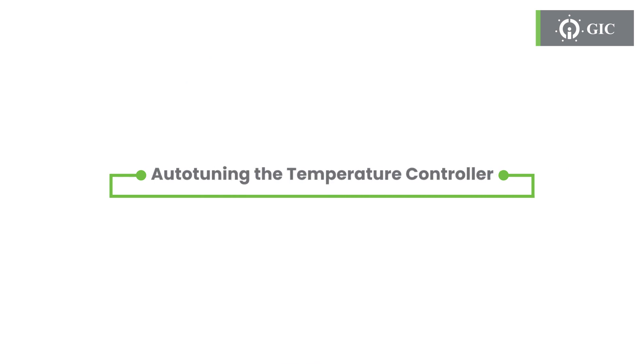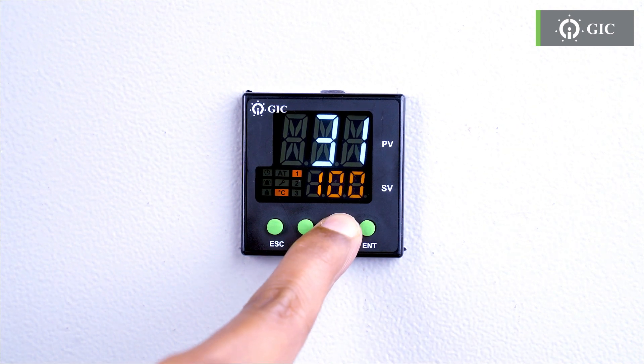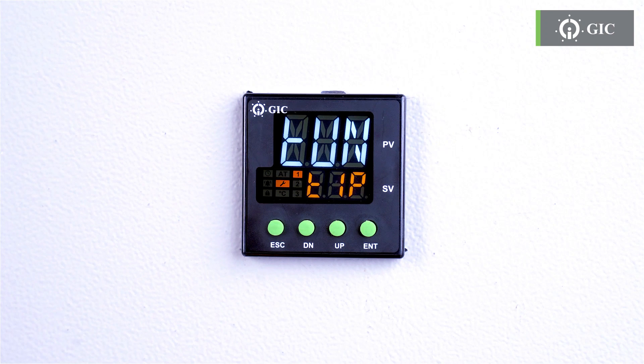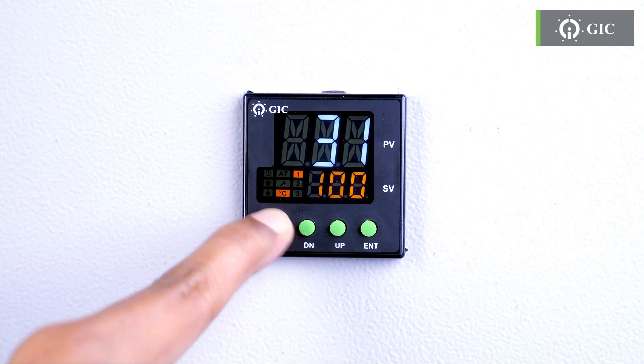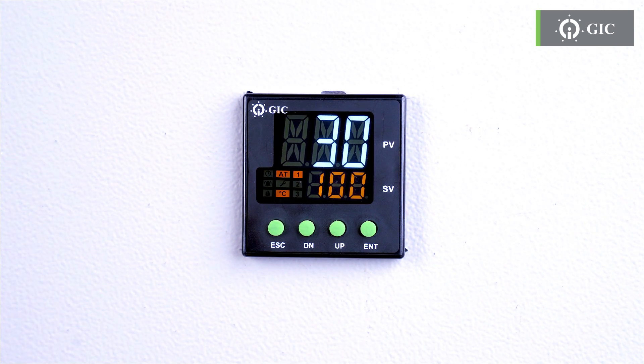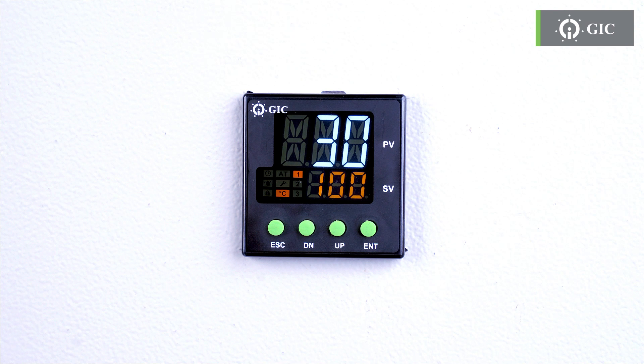You can also auto-tune the product — it helps the controller understand the environment better. Long press the up key for 2 seconds. Then press the up key twice to select tune at first power. Press enter to save, then press ESC to return to the main screen and power cycle the product. After power cycling, a simple display tells you that the auto-tune process is in progress. You'll see the A and T indication blinking until it's complete.